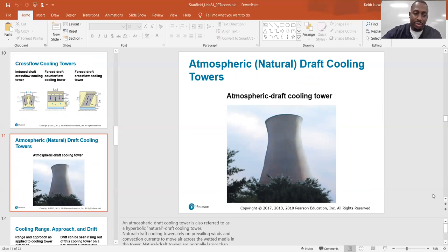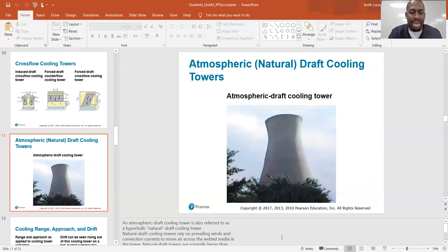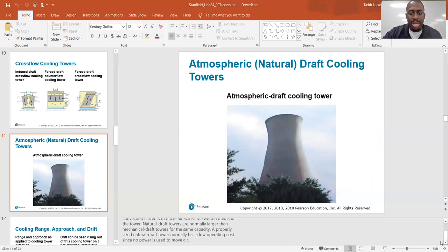Atmospheric draft cooling towers. These are different — they don't require any fans. An atmospheric draft cooling tower is also referred to as a hyperbolic natural draft cooling tower. Natural draft cooling towers rely on prevailing winds and convection currents to move air across the wetted media in the tower. Natural draft towers are normally larger than mechanical draft towers for the same capacity. A properly sized natural draft tower normally has a low operating cost since no power is used to move the air.